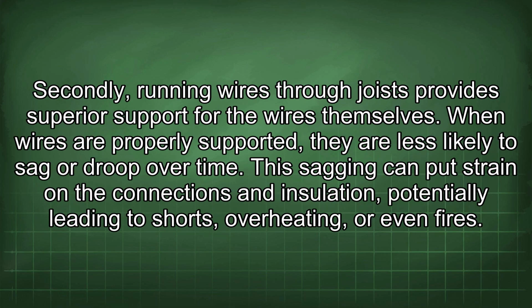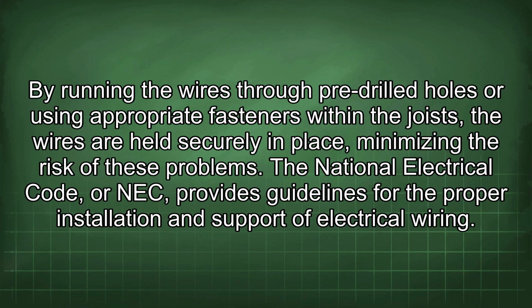Secondly, running wires through joists provides superior support for the wires themselves. When wires are properly supported, they are less likely to sag or droop over time. This sagging can put strain on the connections and insulation, potentially leading to shorts, overheating, or even fires. By running the wires through pre-drilled holes or using appropriate fasteners within the joists, the wires are held securely in place, minimizing the risk of these problems.